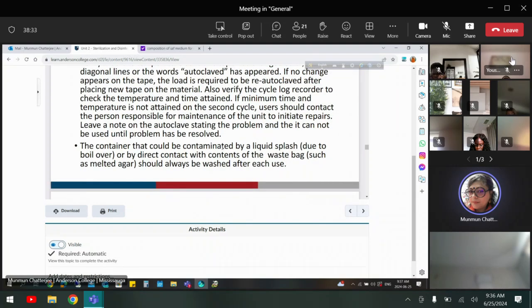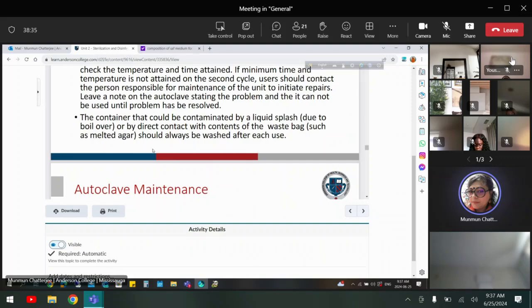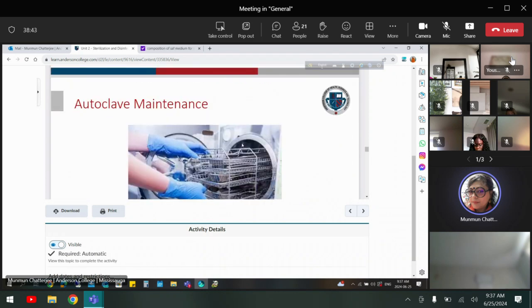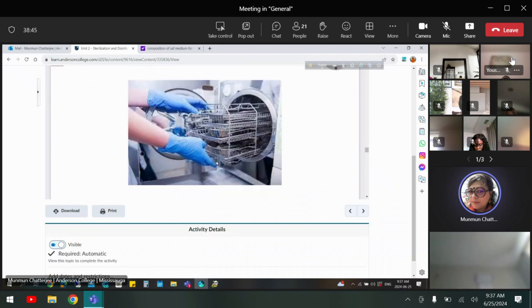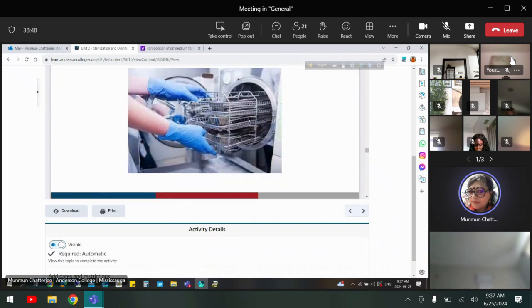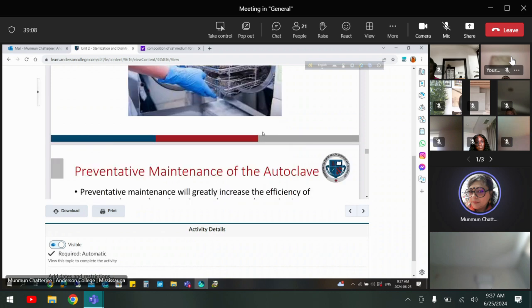If a container could be contaminated by liquid splash due to boil over or by direct contact with the contents of the waste bag, such as melted agar, it should always be washed after use. So if there is any spill, you have to use a wipe inside and clean the autoclave before that. How it's placed: rack by rack, one by one, placed like this, so that one is not touching another one, and there is space in between. And the heavy things will be down, the hard and heavy things, and obviously light things will be on top.